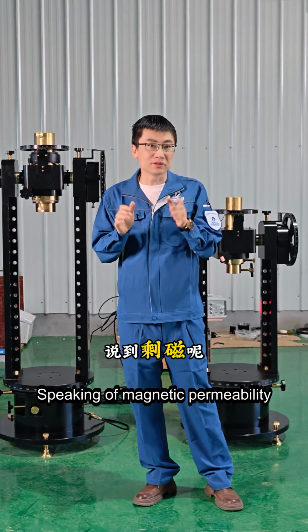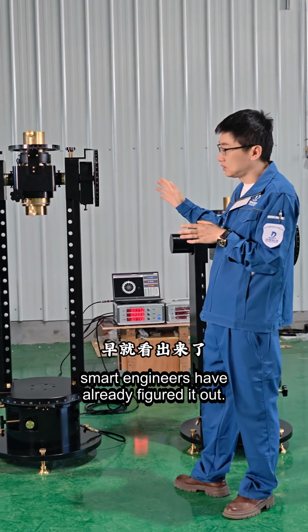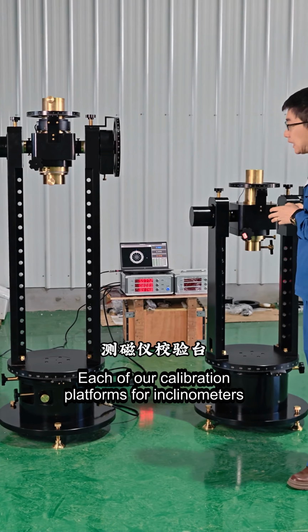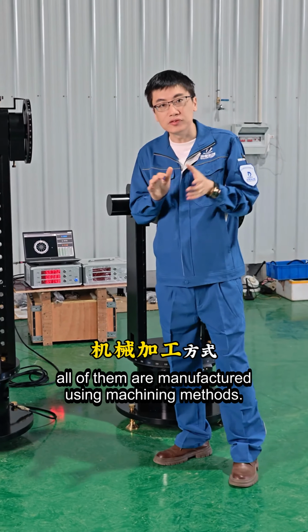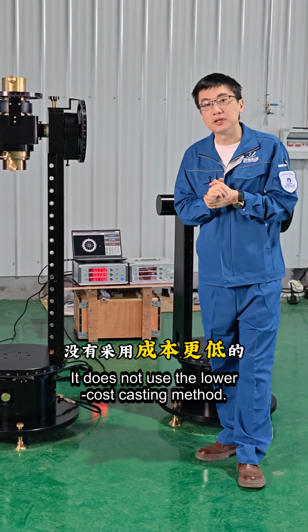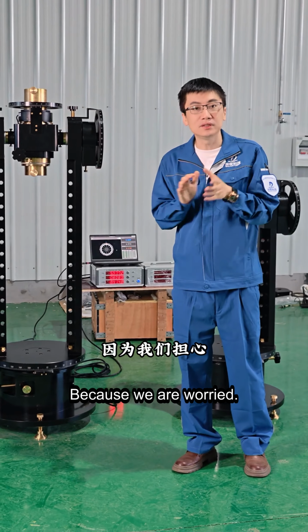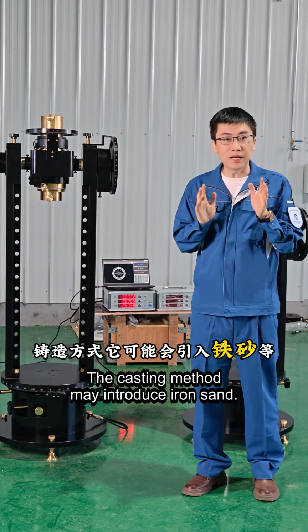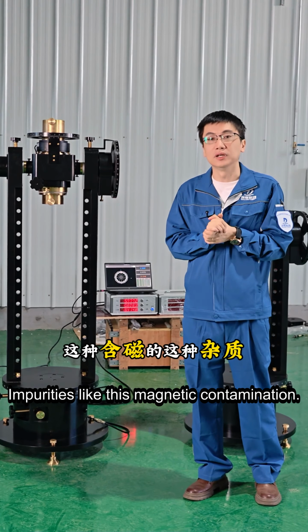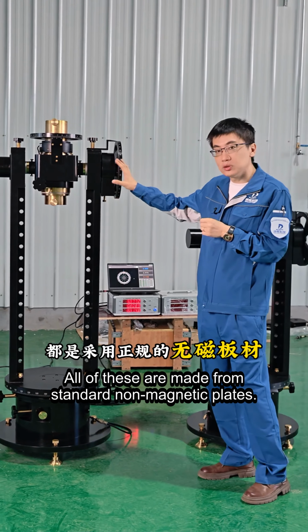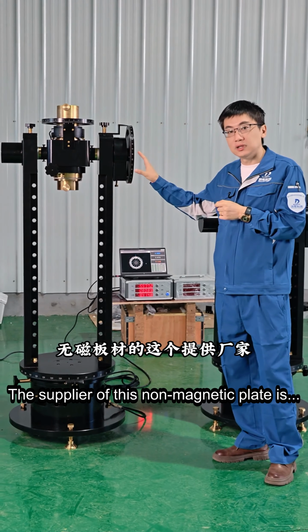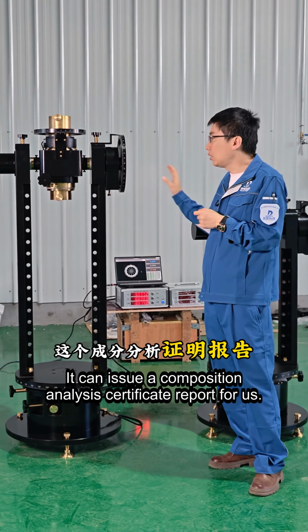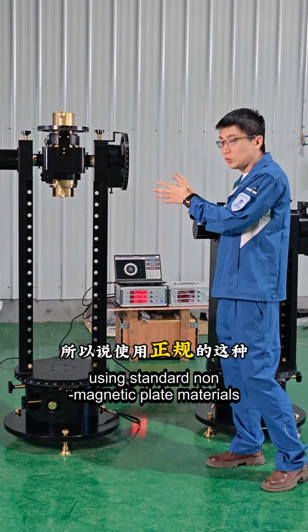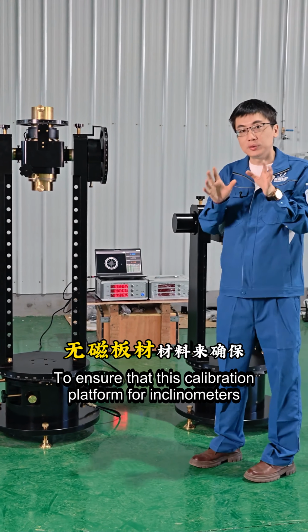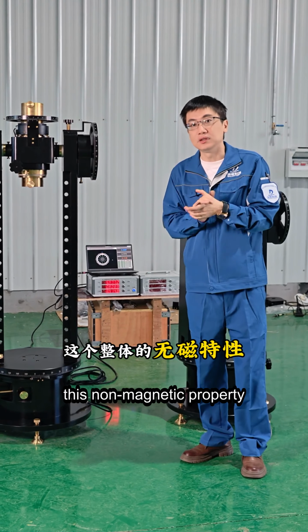Speaking of magnetic permeability, now let's talk about the manufacturing process of our calibration platform. In fact, smart engineers have already figured it out. Each of our calibration platforms for inclinometers is manufactured using machining methods. It does not use the lower cost casting method, because we are worried the casting method may introduce iron sand and impurities like this, causing magnetic contamination. All of these are made from standard non-magnetic plates. The supplier of this non-magnetic plate can issue a composition analysis certificate report for us. Therefore, using standard non-magnetic plate materials ensures the overall non-magnetic property of this calibration platform for inclinometers.